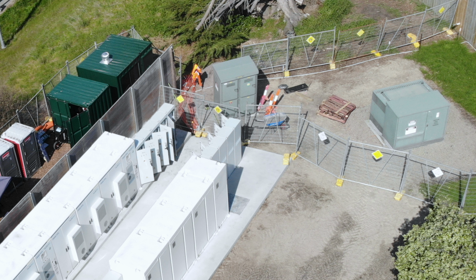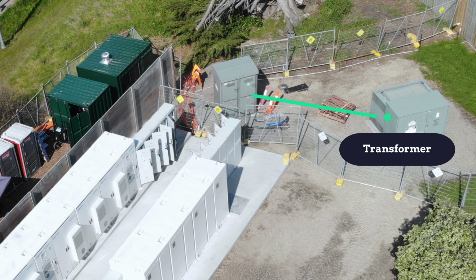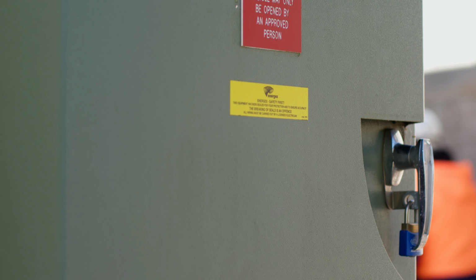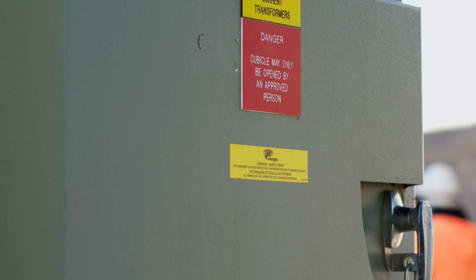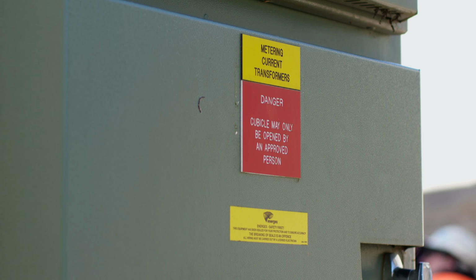From the idea of spatially, we're talking about the transformer being very close to the, what would you call this, the meter? Well, I'd call it a kiosk. Kiosk? Really, it's a distribution board for United Energy. This board previously allowed them to connect generators on site to their board and have control over it, which is why this transformer is the size it is on this site. So when you're saying generators, are you talking fossil fuel? Yes. A diesel gen set? That's correct. During the summer tourist season down here on the peninsula, they have power stabilisation issues.